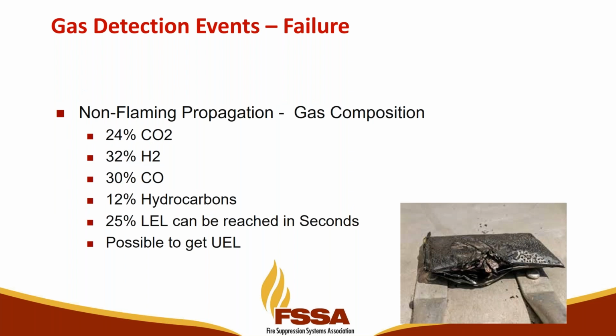Now, if we get into a battery that's failed but not burning, this is a relative composition that we see. A little less hydrogen, a little less hydrocarbons, a little more CO and CO2. But the problem with that failure event is you can reach an LEL within seconds, and you may actually exceed the upper explosive limit within minutes.